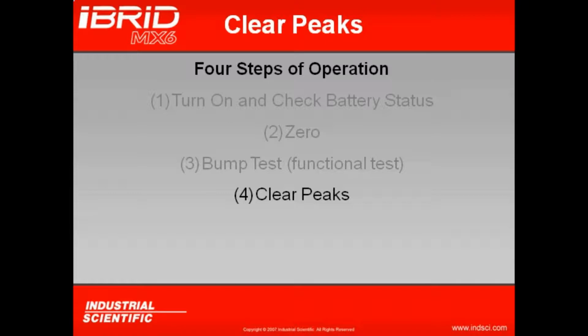Since the instrument will record only the highest toxic and combustible and the lowest oxygen reading since the last time the peaks were cleared, the user would have no idea if they're their peaks or somebody else's peak from another time. Turning off the instrument does not clear the peaks. In fact, removing a battery pack will not clear the peaks. Peaks are stored in something called non-volatile memory, written in the code on the EEPROM. And the only way to clear these peaks is to take it through the peak clear mode.